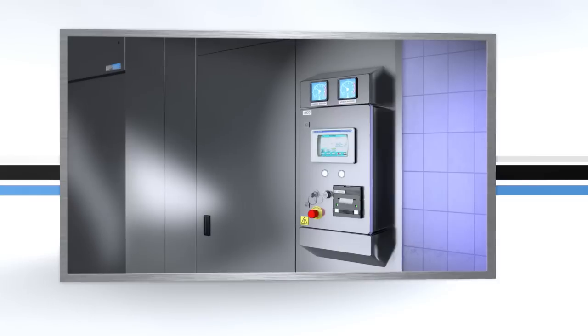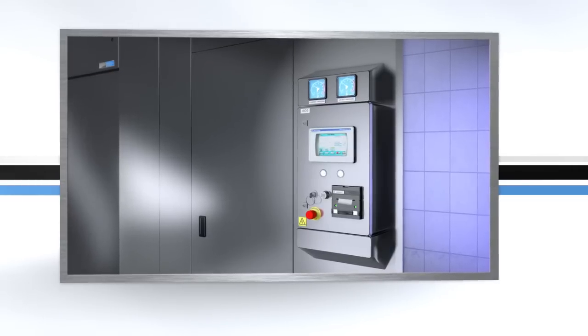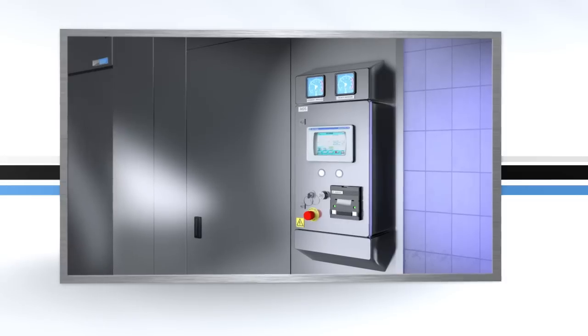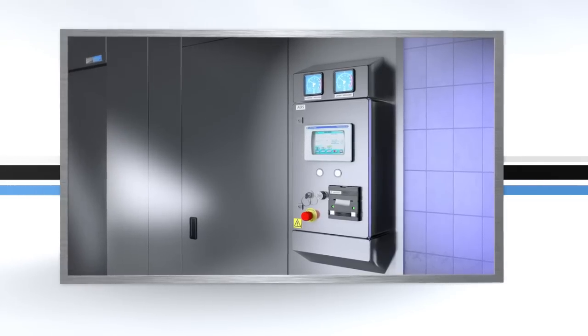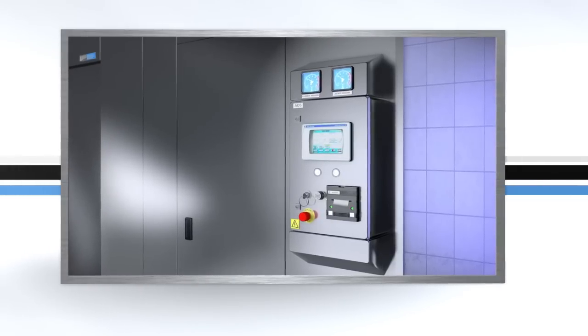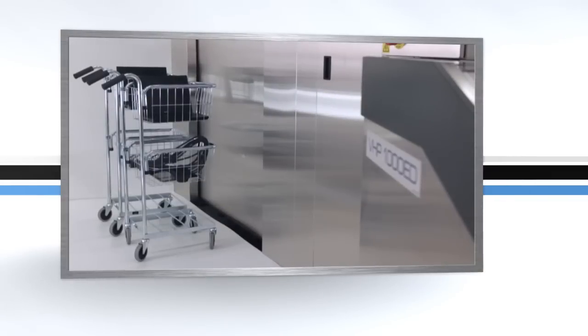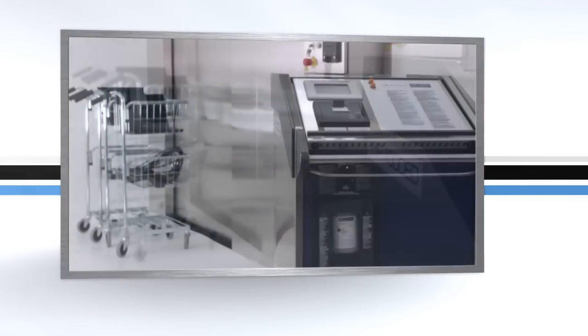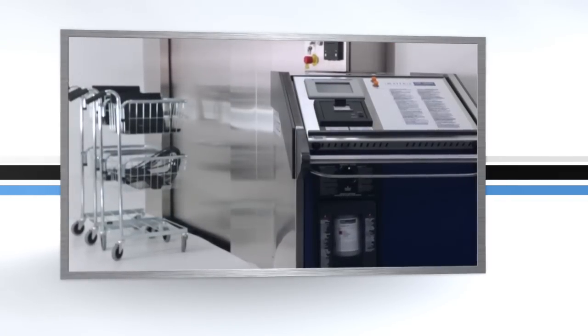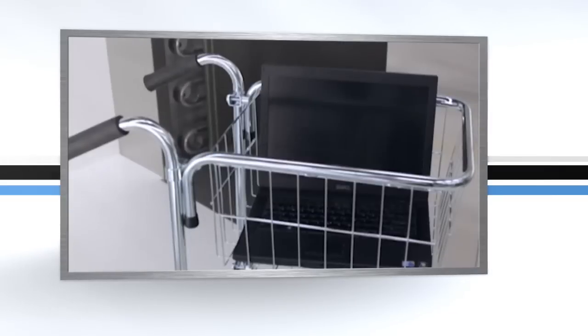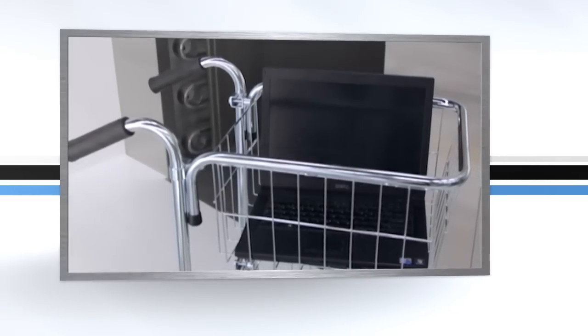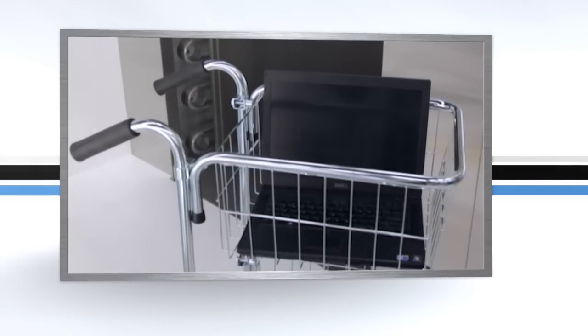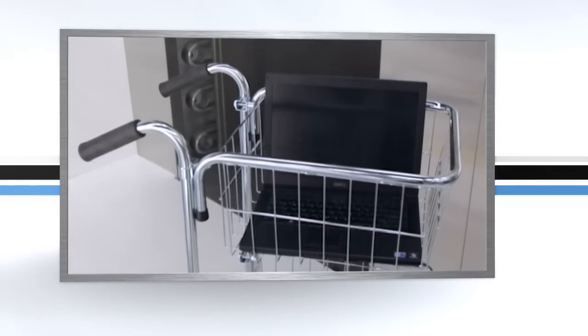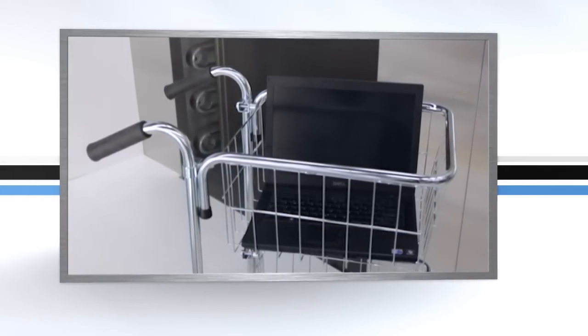An impact printer is provided to maintain records of the cycle process data. The process data can also be easily transferred to a computer or exported to a data management system. Each AMSCO LSS can be used in conjunction with Steris VHP process technology, which utilizes vaporized hydrogen peroxide to biodecontaminate heat and moisture-sensitive goods, such as computers and other electronic devices.